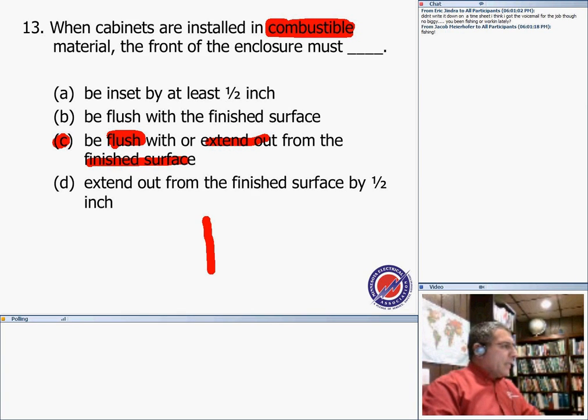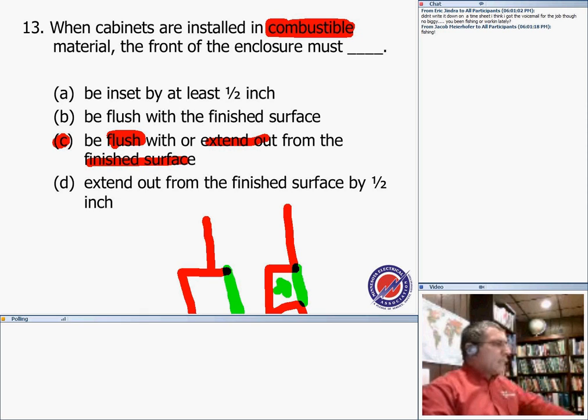Here's your finish. You can have it extended, or you can have it flush, as we all know. And the reason behind this, guys, is that when you put your cover on, the cover will completely shut the whole box down. So if there's a fire here, the likelihood that the fire will spread outside the box is nil. The same thing here. The box cover will firmly sit against the box itself and will not allow the arc and spark to exit or leave the box. Okay, so C is our answer for that one, as you know.